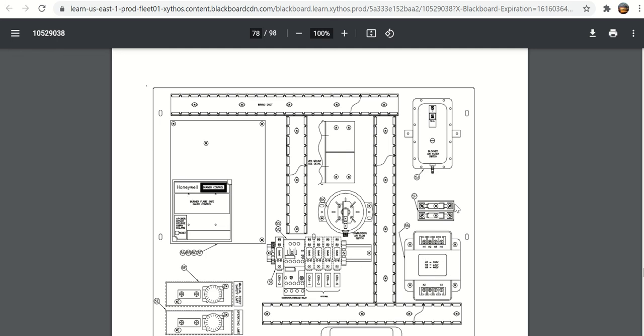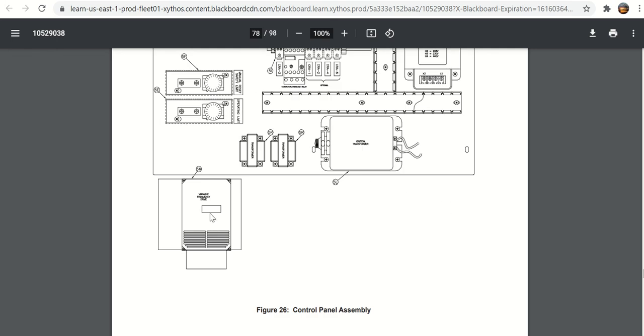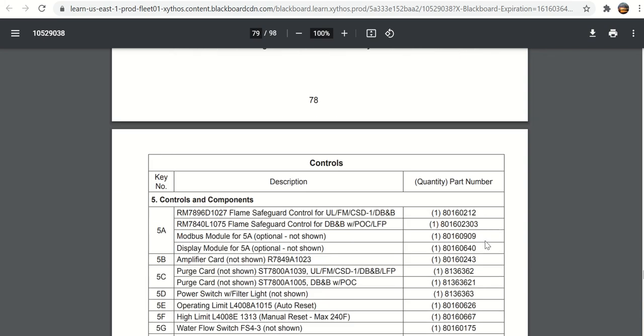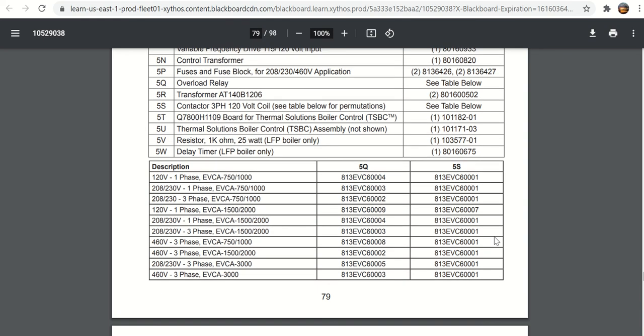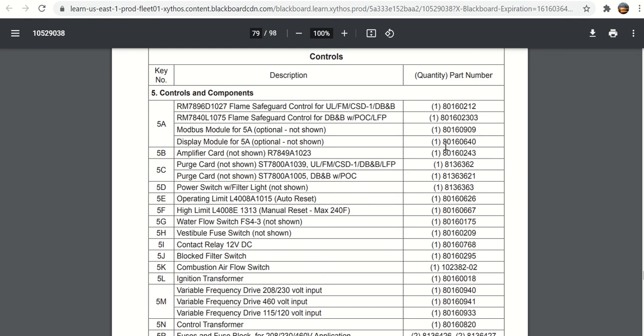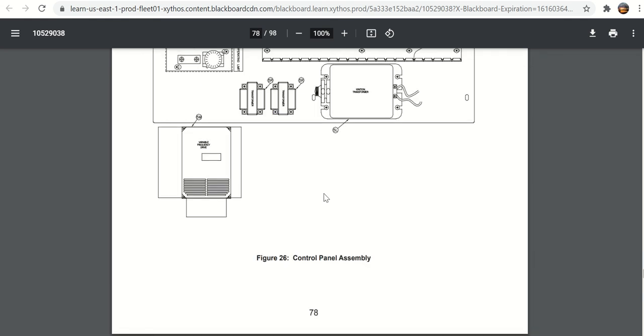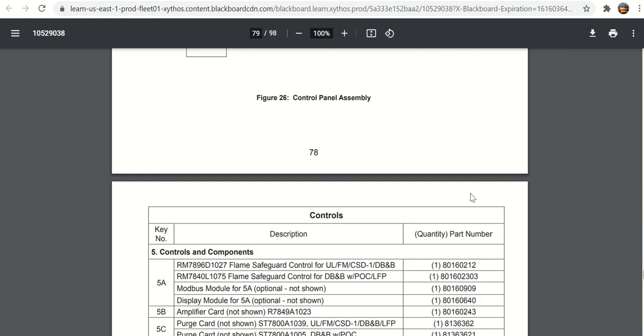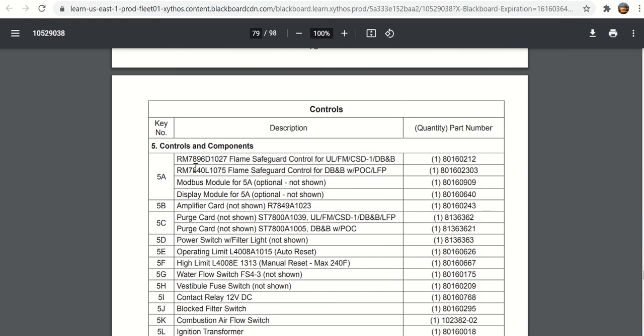Let's see. It doesn't show. There's the VFD. It's actually inside the cabinet. There's your ignition transformer. Of course, the control panel is mounted on the front. One thing I thought was interesting here, when it lists the components for the control panel, there's the flame safeguard. It does list an RM7840L, which is a full function programmer, if you remember from your traditional flame safeguard lesson. That is available if you had the need for POC, proof of closure.